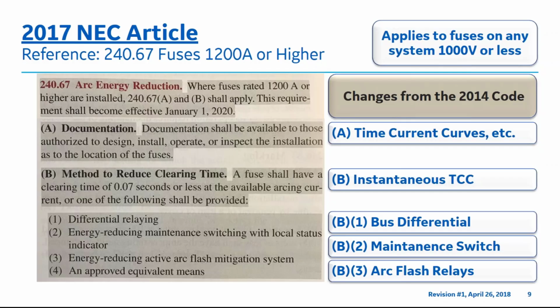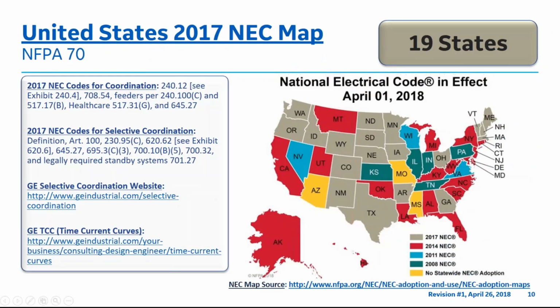IEEE is the owner of the arc flash calculations in partnership with NFPA, OSHA, etc. Again, this presentation is based upon the IEEE 1584-2002 arc flash equations. Here is a picture of the 2017 NEC map, and there are 19 states that have adopted the new code. In addition, the NFPA website link is provided at the bottom of this slide.